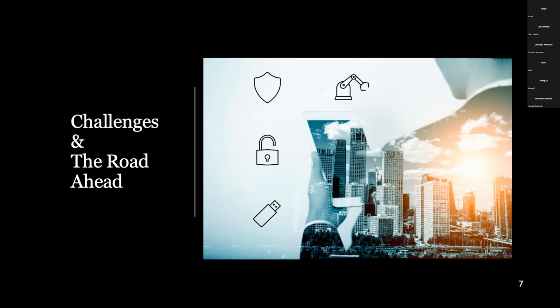Another reason often overlooked is that the sensors themselves, the ground level devices, tend to go bad after a certain period of time. We're looking at a system that works 24/7, and it's a given that it's going to go bad—a temperature sensor, after working maybe 2 or 3 years, is going to drift, and its values will become inconsistent. That needs to be checked regularly, and old equipment should be overhauled and upgraded to the latest technologies.